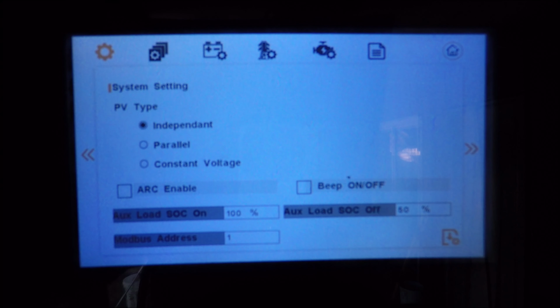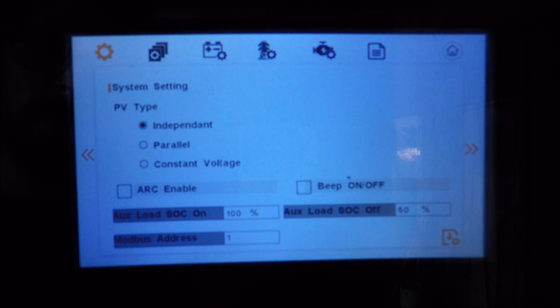Auxiliary load on and off. There is a second AC output on the inverter. This can be turned on and off based on the battery state of charge. This is very helpful when output 1 is tied to your critical loads and output 2 is tied to non-critical loads. For instance, you could put a refrigerator, your well pump, and your furnace on output 1 as critical loads, but your TV and microwave, all the rest of the power in your house, could be on load 2, and if there's a power outage, if your batteries drop, let's say, to 80%, it simply turns off all those other loads and keeps power going to your essential loads.